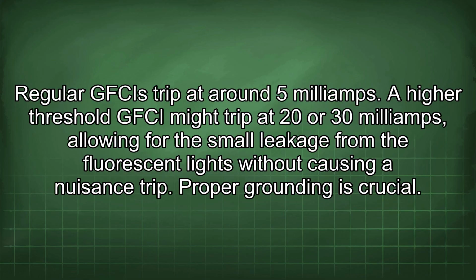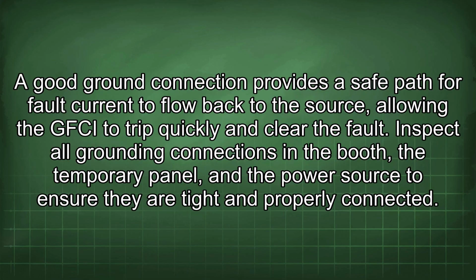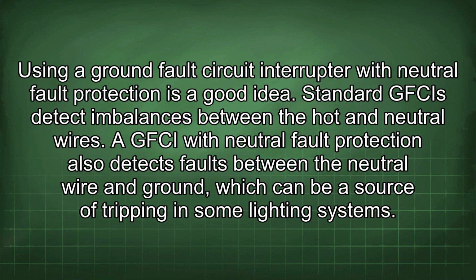Proper grounding is crucial. A good ground connection provides a safe path for fault current to flow back to the source, allowing the GFCI to trip quickly and clear the fault. Inspect all grounding connections in the booth, the temporary panel, and the power source to ensure they are tight and properly connected. Using a ground fault circuit interrupter with neutral fault protection is a good idea. Standard GFCIs detect imbalances between the hot and neutral wires. A GFCI with neutral fault protection also detects faults between the neutral wire and ground, which can be a source of tripping in some lighting systems.